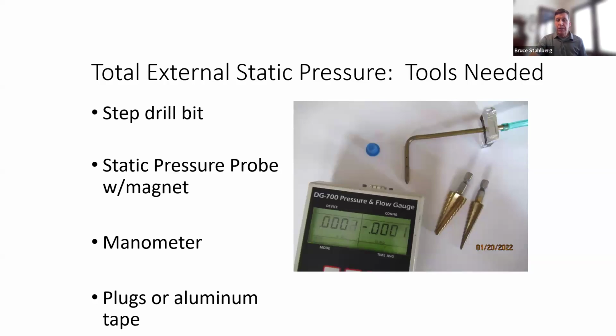In fact, the Energy Conservatory now has a new drill bit that goes in, I think, 1/4 of an inch, and you can't go any further. So that's another way to prevent that from happening. We need a static pressure probe with a magnet. That's the one on the upper right hand with the green hose on it. A manometer, which is a pressure gauge. All HVAC contractors should have pressure gauges. All weatherization people certainly have them. And then we want something to plug up the test ports.